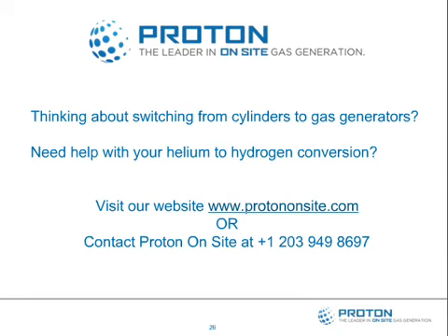Another listener says they have oxygen cylinders that supply their sulfur analyzer and will be supplying their upcoming CHNS analyzer. Are there any oxygen generators on the market? Yes, there are. I chose not to discuss oxygen specifically because, as far as the analytical lab market goes, it is a smaller section of the market. But there are a number of oxygen generator solutions out there. It depends on your usage rate and purity primarily when dealing with oxygen. If I get your contact information, I can point you in the direction of some of those supply sources.